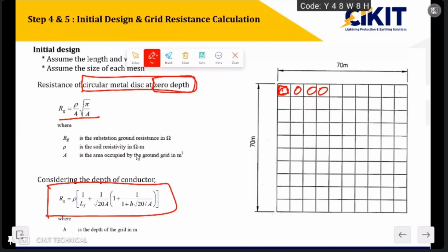Here you can observe that the three important parameters are Lt, that is the length of the conductors, A, the overall area which is available for this earth mat, and h, the depth of the grid. So whether I am going for 500 mm burial or 600 mm, h is the depth of burial, A is the area availability, and L is the total length of the conductor which is used for this earth mat.